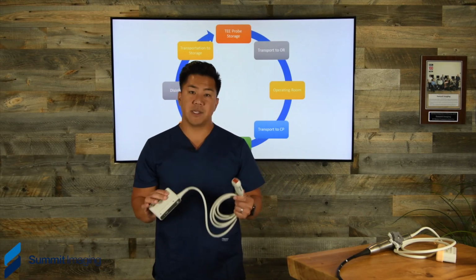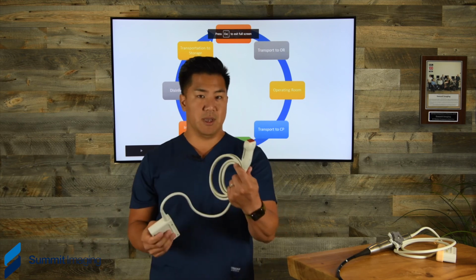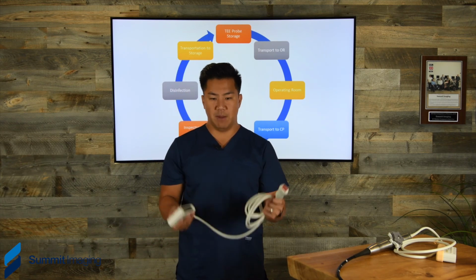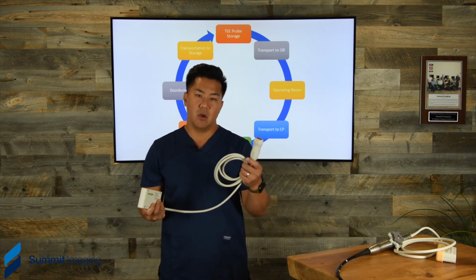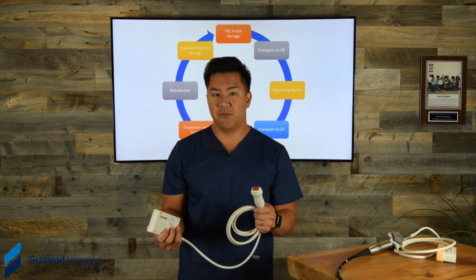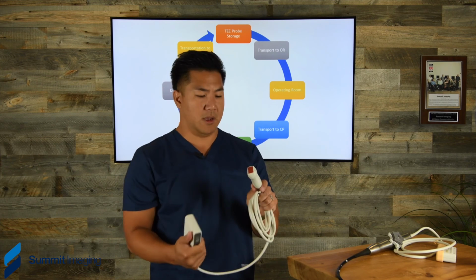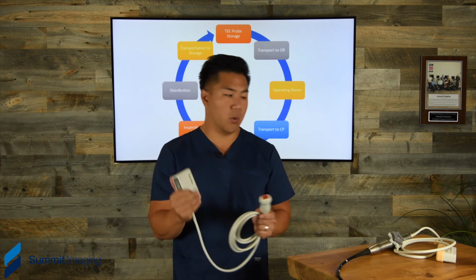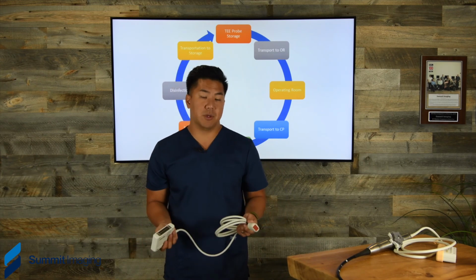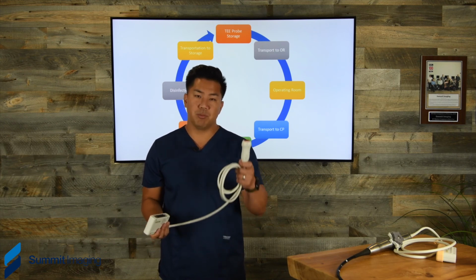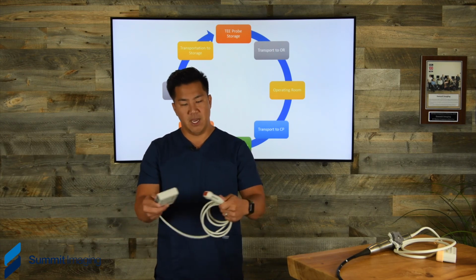So now we've got a standard probe, just a cardiac sector transducer, and we recommend the same thing: coiling it up, holding the can in one hand, holding the transducer in the other. The difference is the crystal is right on top instead of facing forward like the TEE probe, but the same issues apply, in that you want to protect this crystal, especially from hitting the can.